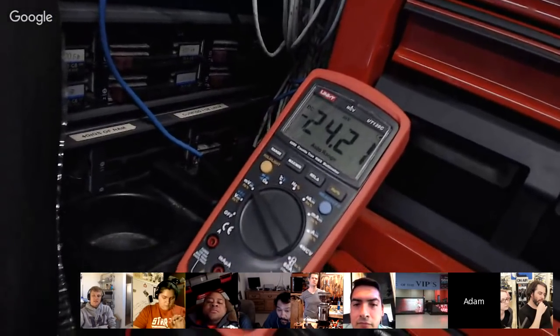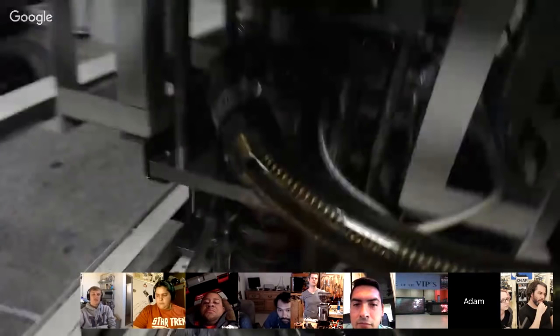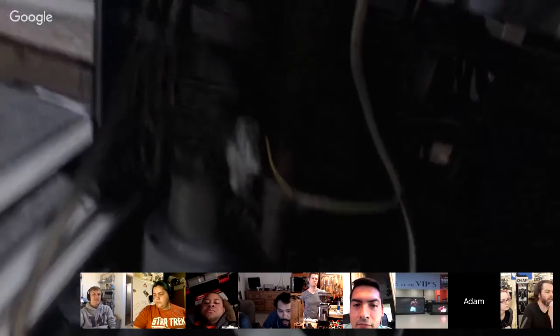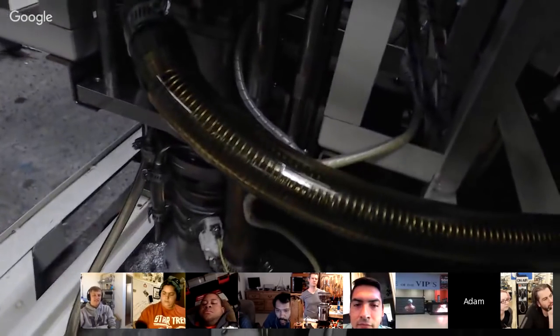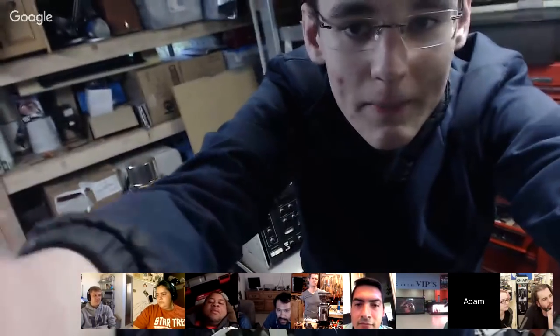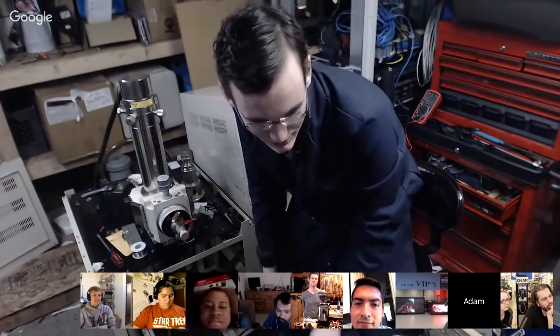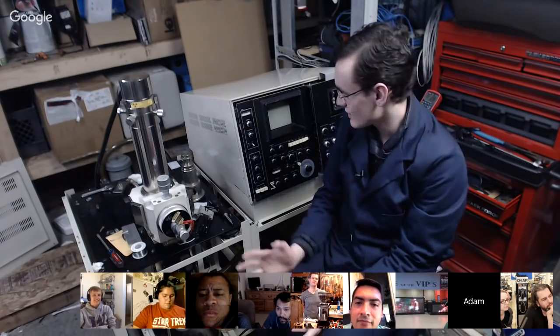And that's how I'm going to have to find this thing, because every screw or nut you see down here is basically one vacuum seal. And there's, I think, 40 or 50 O-rings inside of this machine total that I have to check each one individually. Doing that is going to be somewhat of a challenge, but it's what you need to get high vacuum systems working. This is something I've had to do on vacuum systems before. On those, I've had better gauges and real leak detectors, but I had to make my own for this one.